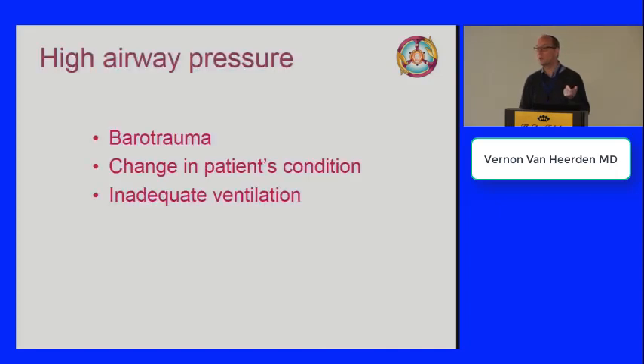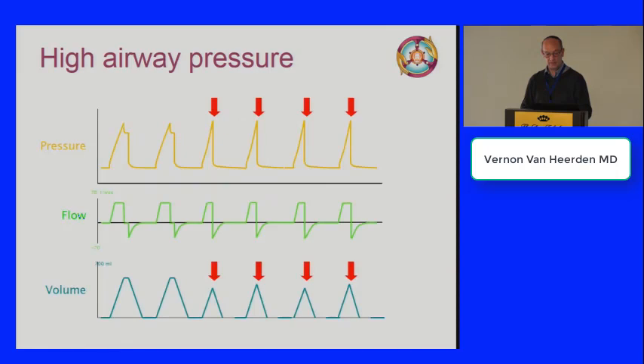Okay, so why do we care about it? High airway pressure, so what? It might just be that the alarm is set a bit too low, but what we're concerned about is that we might be causing barotrauma to patients, so we want to avoid that. The fact that we have an airway alarm might mean that there's been a change in the patient's condition, like there's a sputum plug which needs to be suctioned out, there's a pneumothorax which needs to be dealt with, or that we're causing inadequate ventilation because the airway pressures are rising and the tidal volumes being delivered are too small. So that's why we care about airway pressure, because it's an indicator of something else which might be going on.